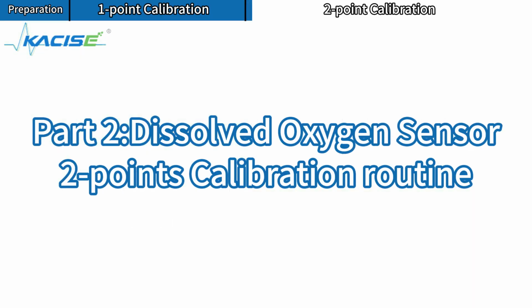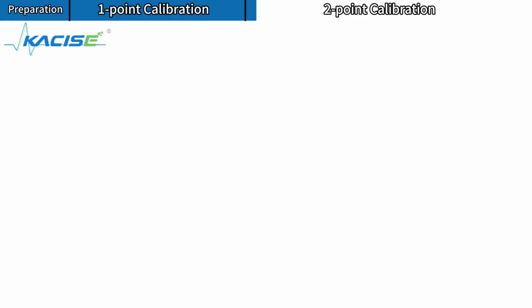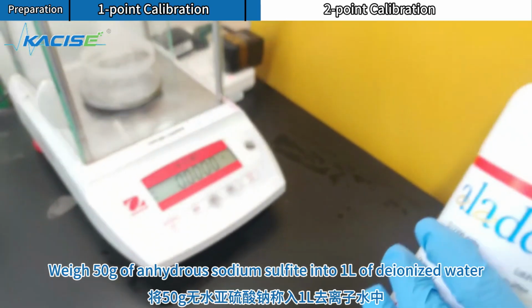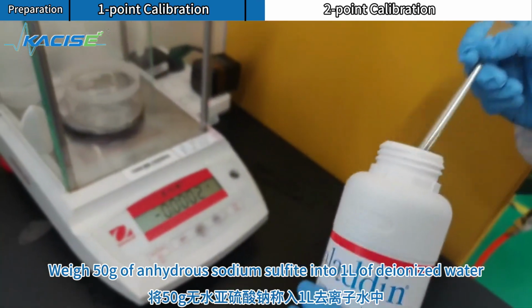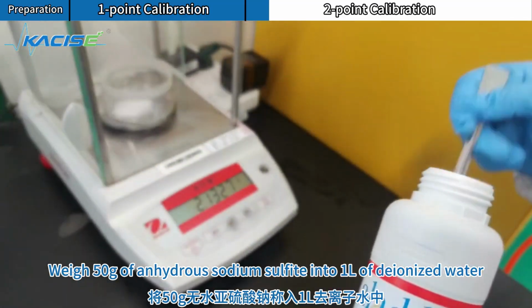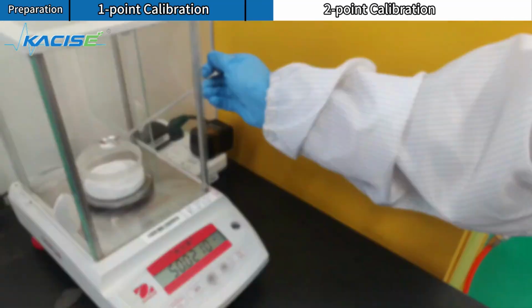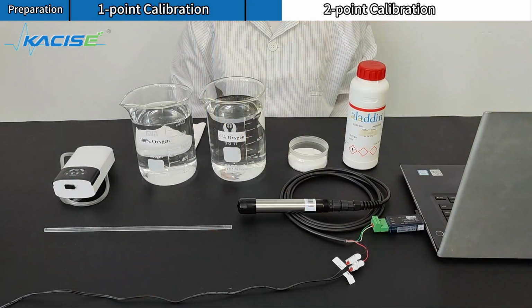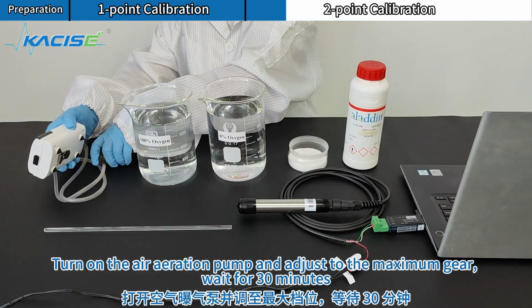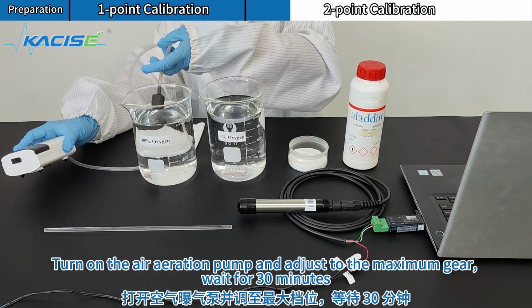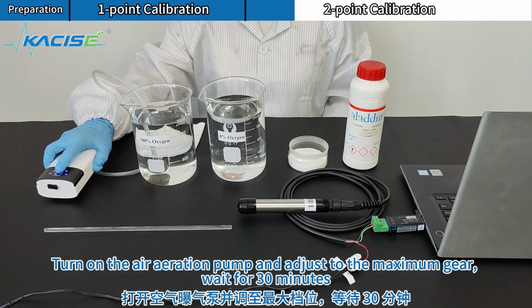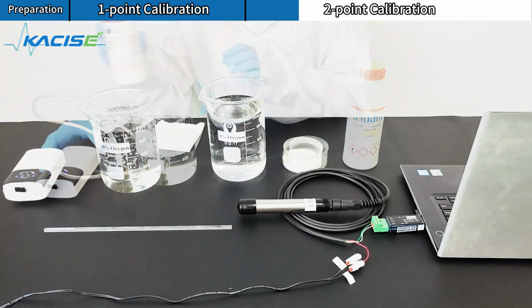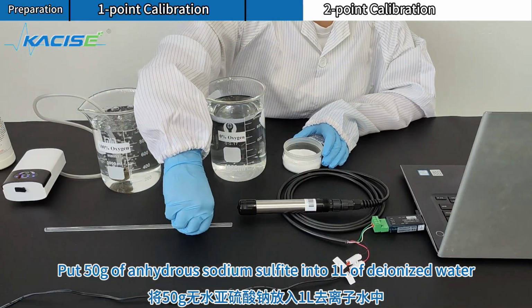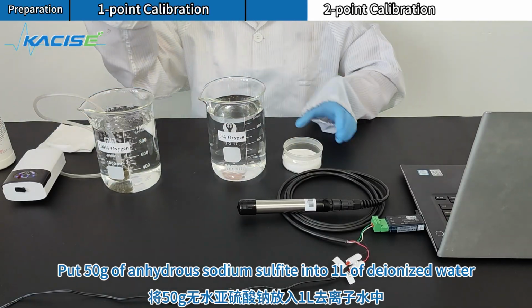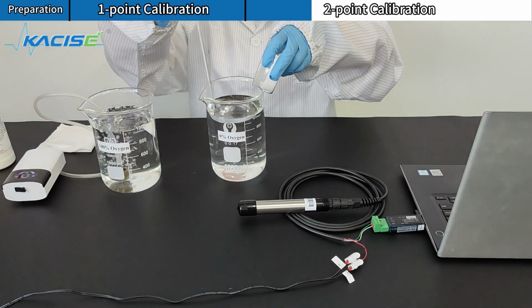Part 2. Dissolved oxygen sensor, 2-point calibration routine. Weigh 50 grams of anhydrous sodium sulfite into 1 liter of deionized water. Turn on the air aeration pump and adjust it to the maximum gear. Wait for 30 minutes.